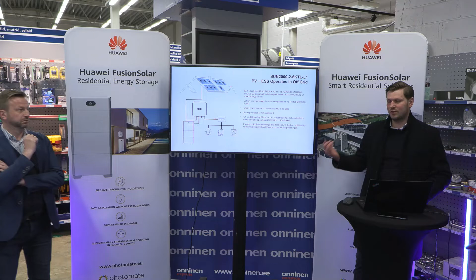Also, the diesel generator usually doesn't produce exactly 50 hertz — it has some frequency deviation, and the inverter is very sensitive to frequency changes in the grid, as specified in the grid code. So you might have, for example, 50.5 hertz from the diesel generator. For the loads it doesn't matter, but for the inverter it does — it will start to decrease the output power. That's new information, thank you.